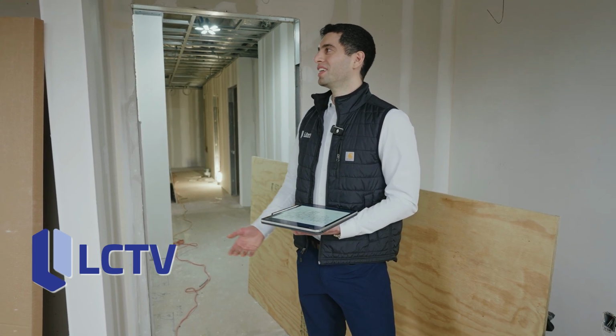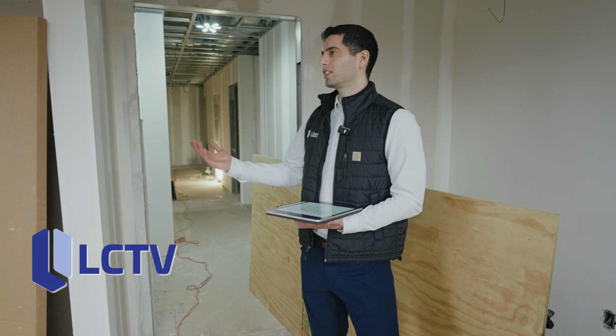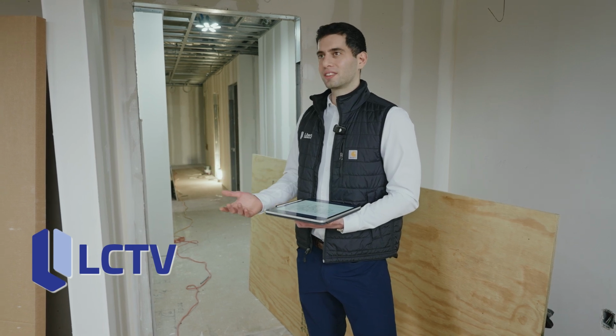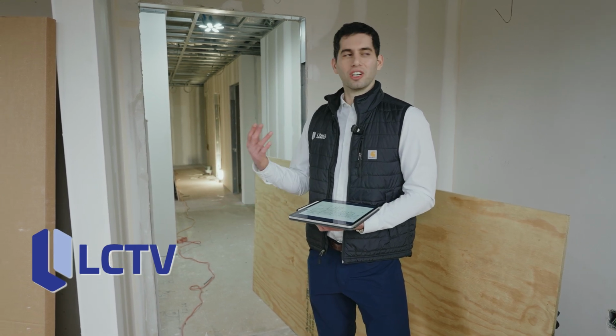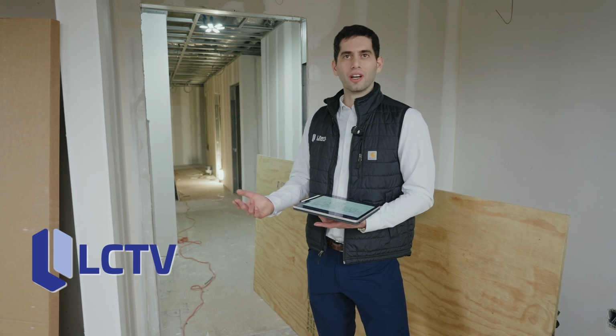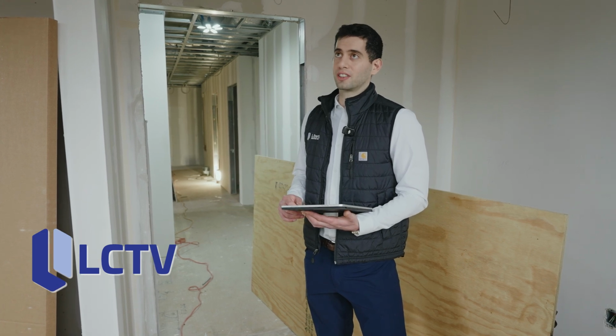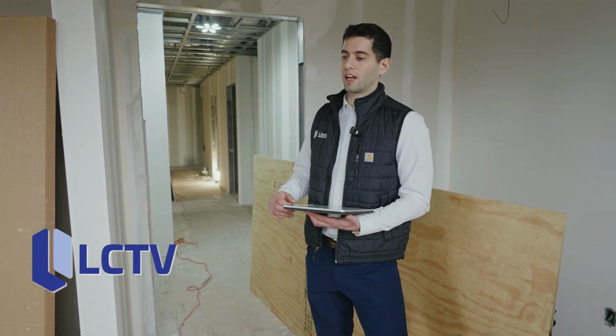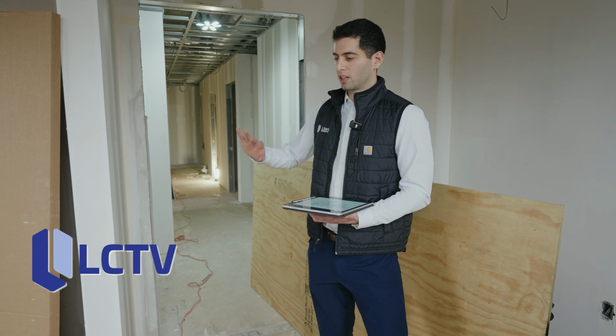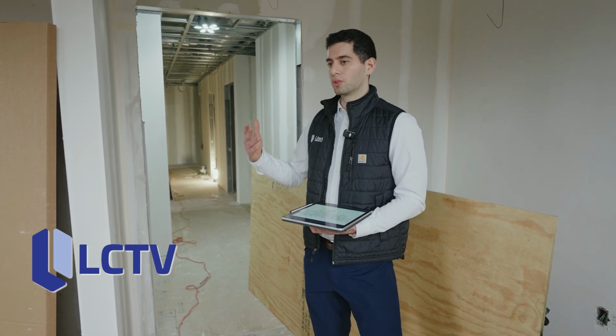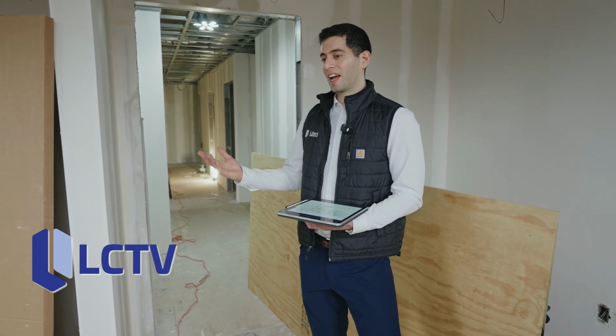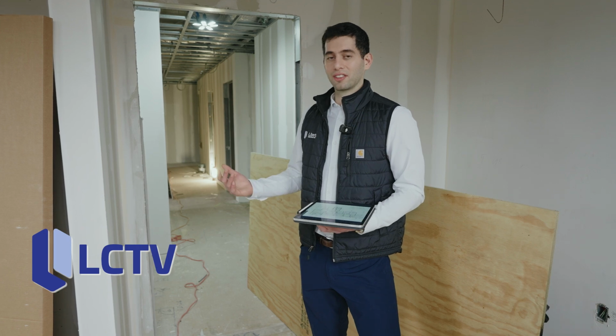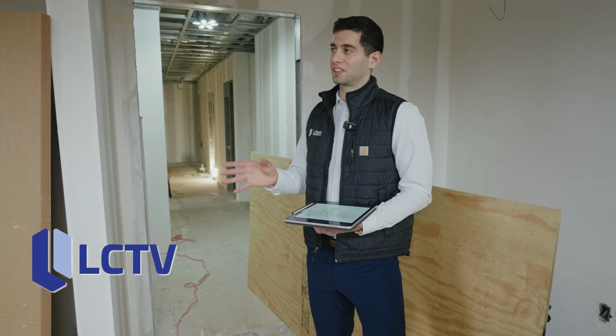Then the new leasing agent just says, last minute, oh, you actually need a sub-meter. Well, that could have a long lead time. If it's already been hooked up, that's a change order. I have one instance where they didn't tell the client at the beginning, only a little later, that they actually need a new Pepco meter socket, and that could have a 3 to 6 month lead time. It's not just the sub-meter itself.